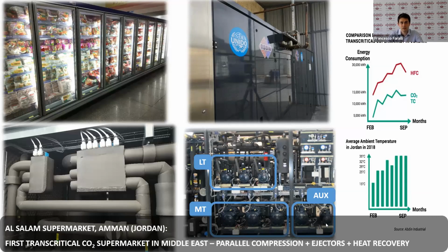In this case, we have the first supermarket using CO2 in the Middle East, installed in 2017 in Jordan. The installer made a comparison between 404A, so the previous system that was installed there, and the new transcritical CO2 system during the summer period. And actually what they found out is that even if the mean ambient temperature was 35 during summer in Jordan, there is a quite significant benefit in energy consumption between CO2 and the old HFC system.